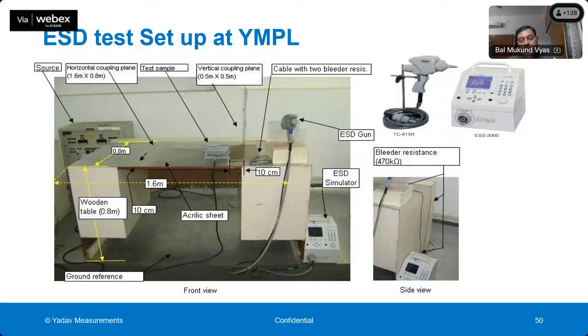So there are two types of tests. One is direct discharge of the electrostatics, and another is indirect discharge. In indirect discharge, the high voltage is discharged on a metallic plate which is kept close to the meter body, 10 centimeter away, and the heavy current will flow through this metallic plate, which will cause the magnetic field, and the performance of the meter is checked due to this discharge.